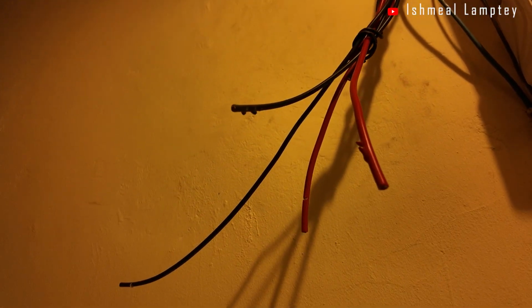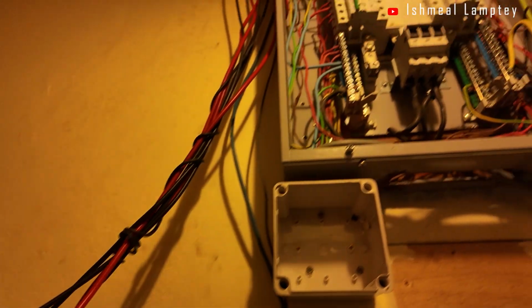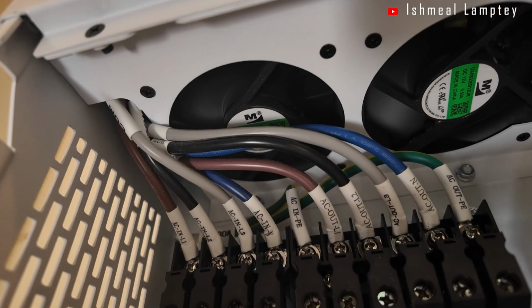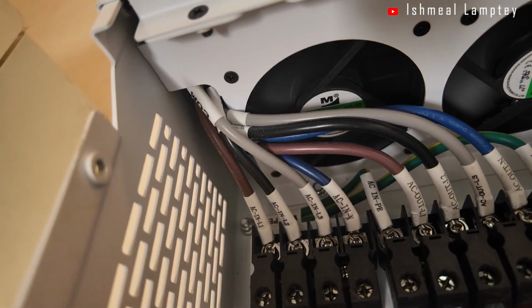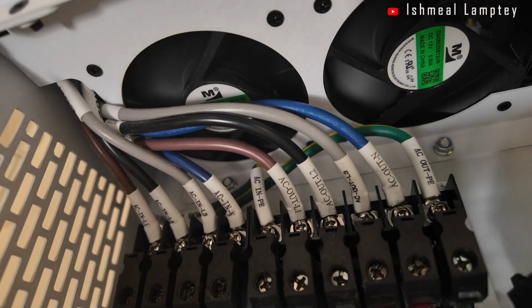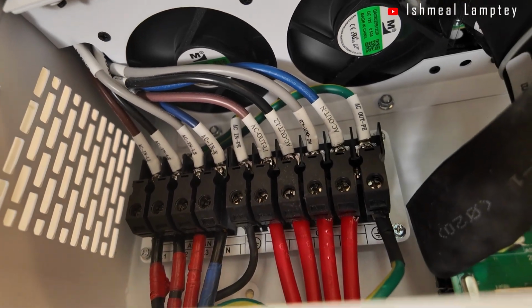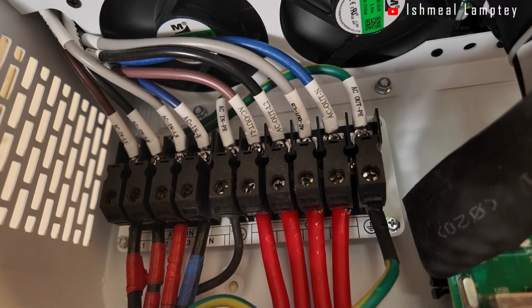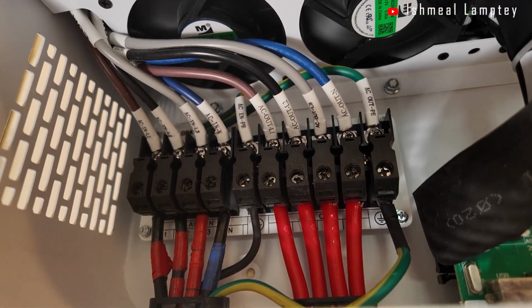Now also for the setup of the inverter, there are a couple of things that we did. So the inverter has an AC input. So AC input is basically power coming from the grid, which is coming into the inverter. Now that is able to do two things. It's able to charge the battery, and it's also able to power the house. I'll come back to explain that.